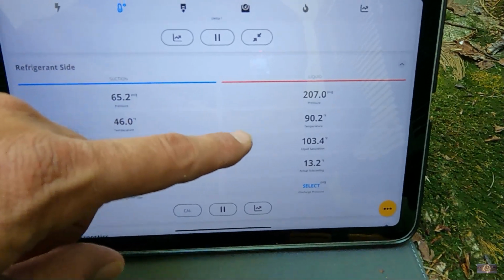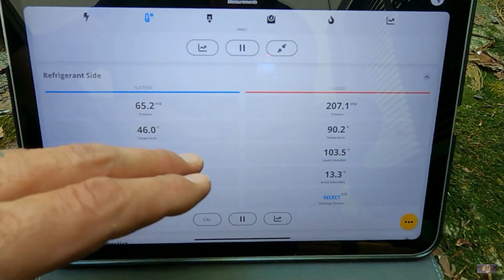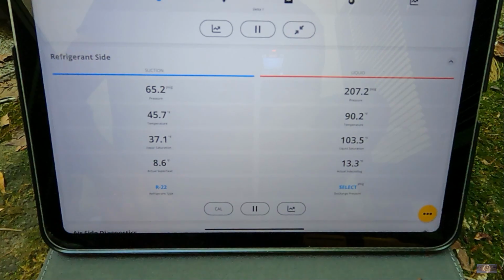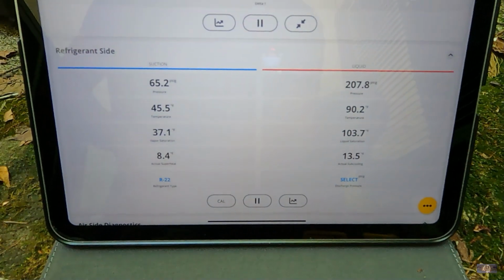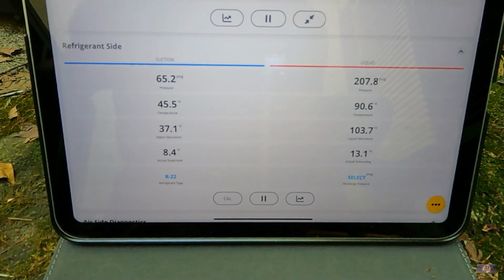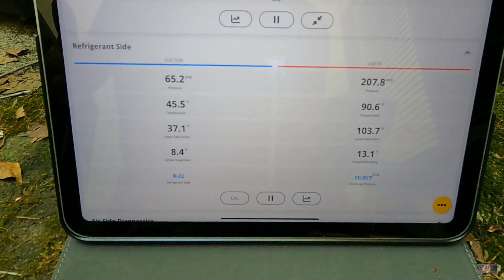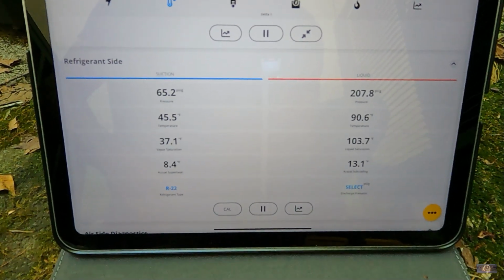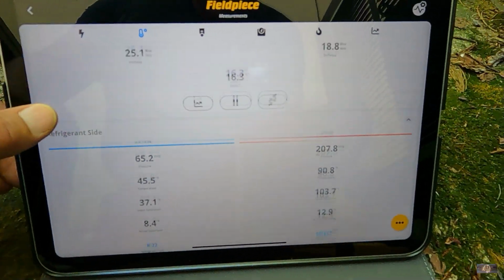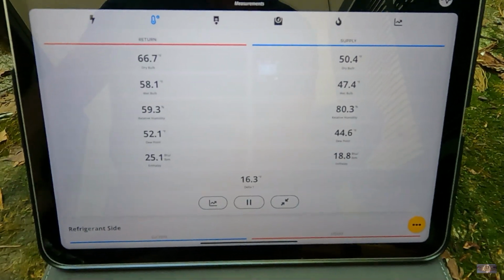on the head. I really can't expect much more from this unit because it is, like I said, oversized. It's a 2.5 ton unit on a 1.5 tons of ductwork. I got it dialed in about the best I could doing these maintenances year after year. So let's see, the split's still about the same, 16.3.